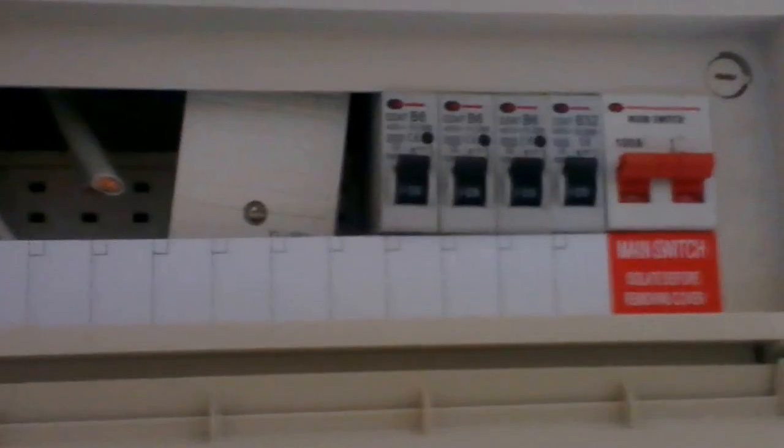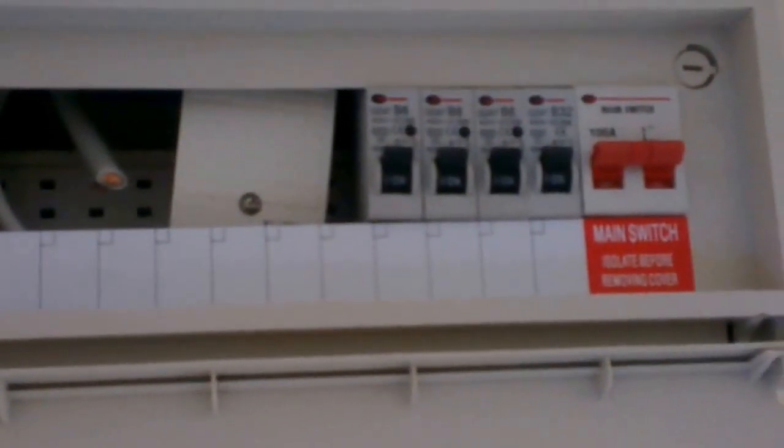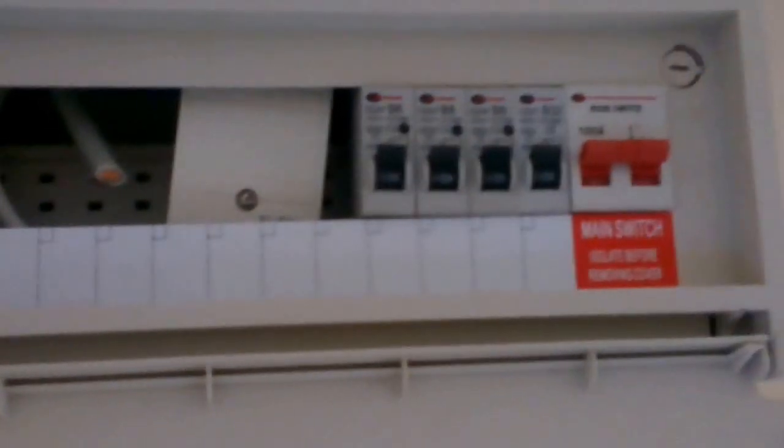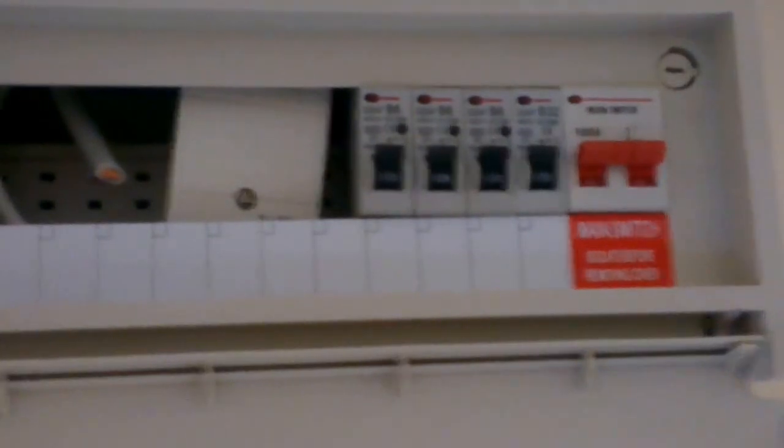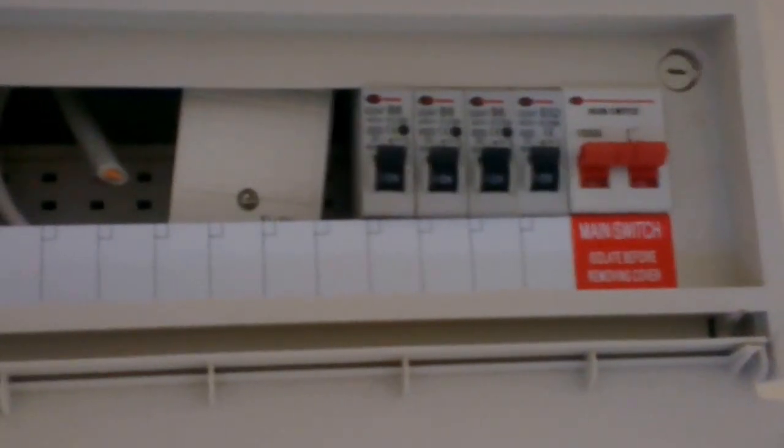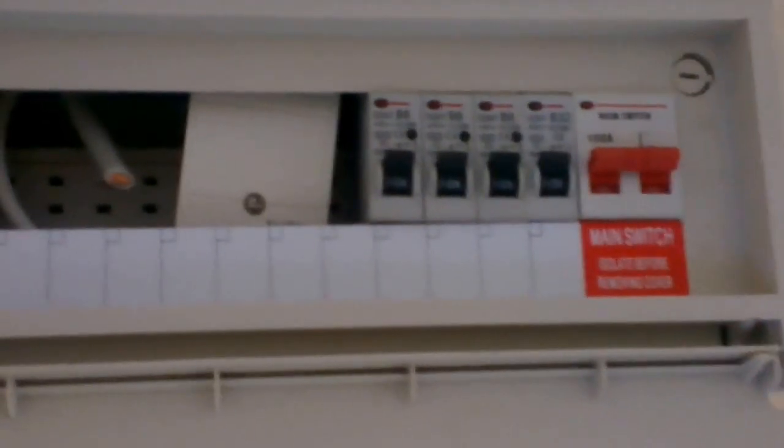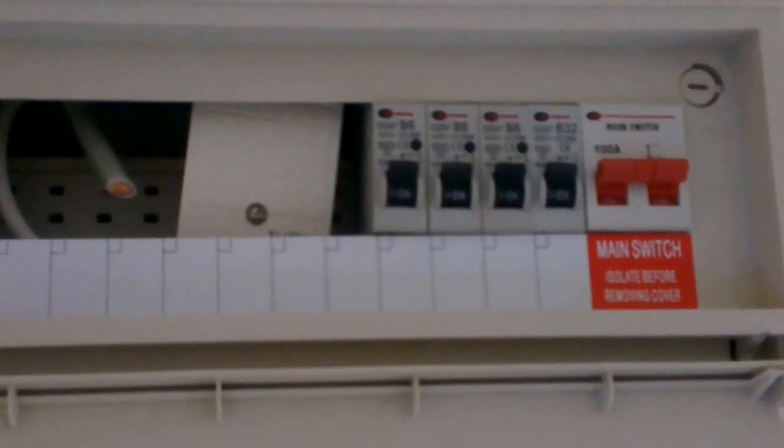But if you have a fault, you'll hear a bang, maybe see a flash out of it, and it'll flick it off again. In that case, you'll need to get a qualified electrician to look at it because there's a short circuit somewhere in the system. And you need to disconnect the fuse board and test all the cabling on that circuit.